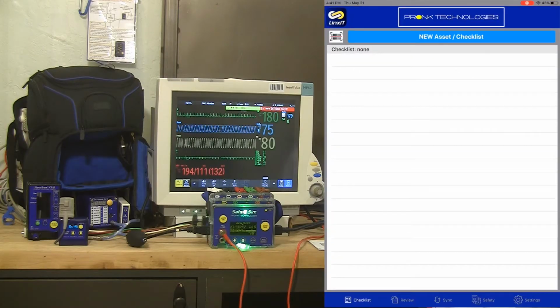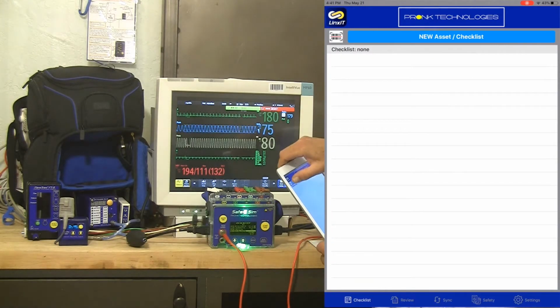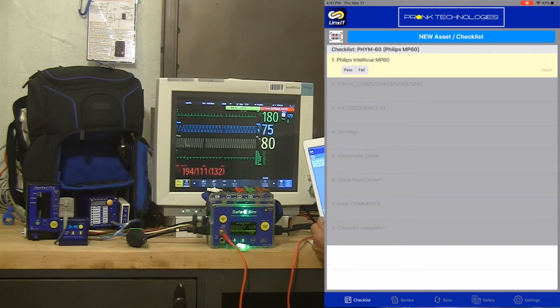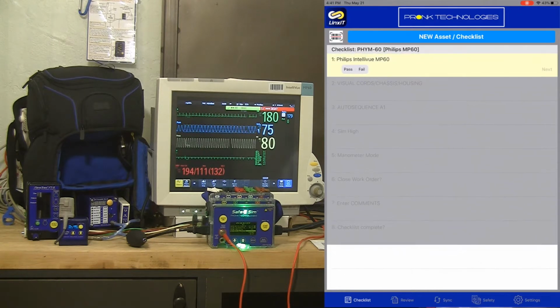All I have to do is launch the app using the camera built into my iOS device, barcode scan the medical device, and that can immediately pull up a checklist for that device type. In this case, the Philips IntelliVue MP60. And from there, I've got a complete checklist for that device type, and I can run those test steps from my iOS device, indicating pass or fail, and also automatically controlling the test devices.